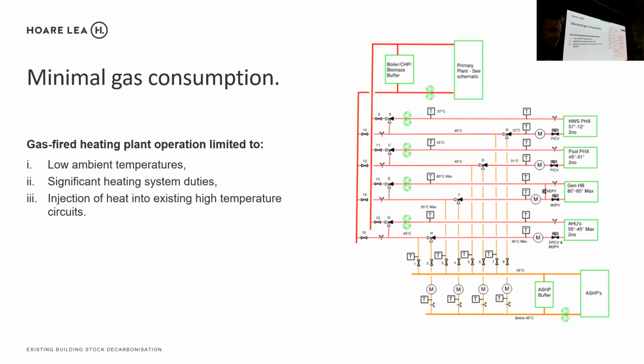And for the space heating circuits, basically, they don't need to operate at 80 degrees. They're compensated circuits based on the outdoor temperature. So whenever the calculated compensated flow temperature was below 45 degrees, we just diverted it through the air source installation.